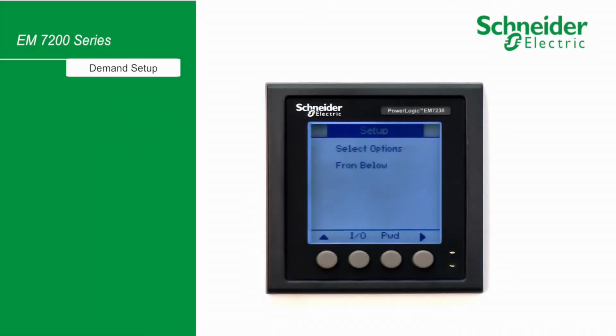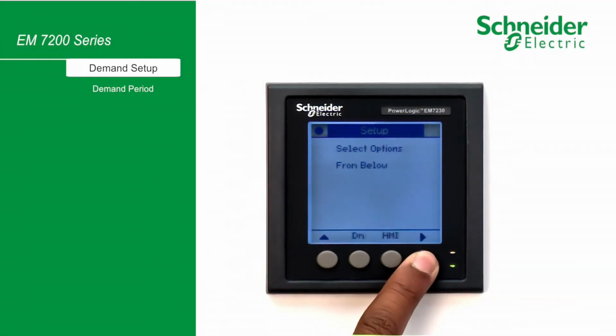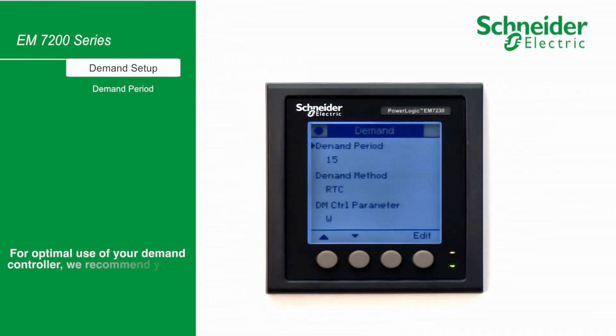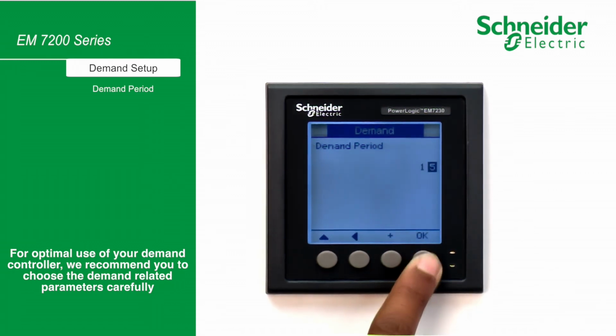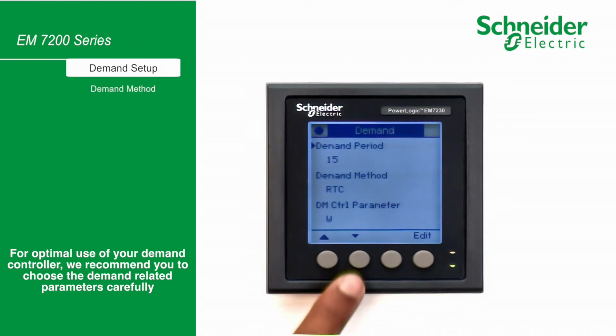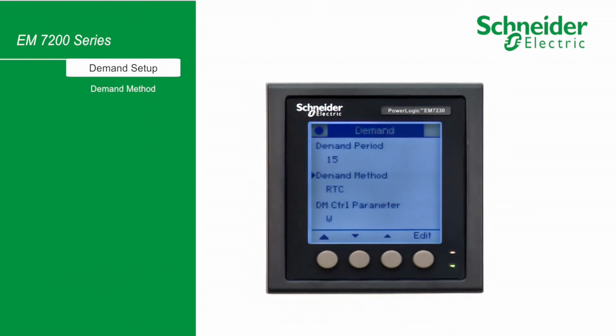Demand Setup. From Setup page, navigate to Demand menu. It is Demand Measurement Cycle. Demand period can be set from 1 to 30 minutes. Let's set for 15 minutes. Then press OK. Demand method is a demand measurement technique.